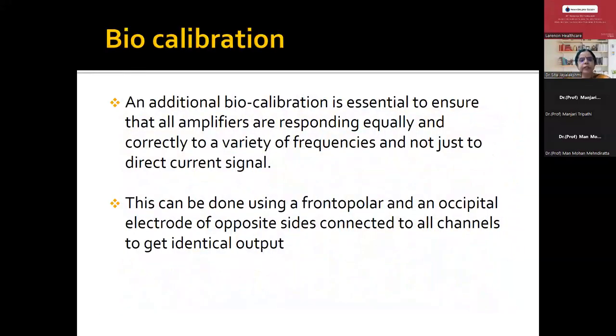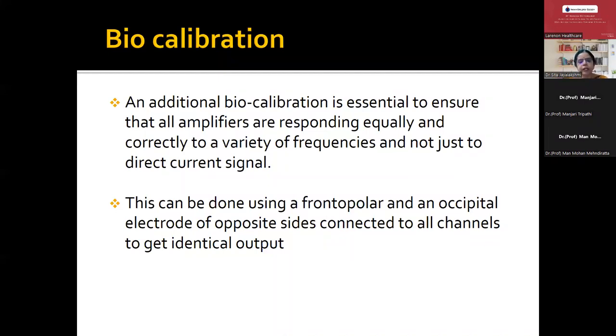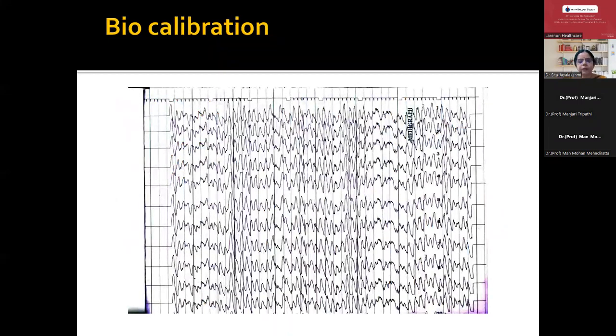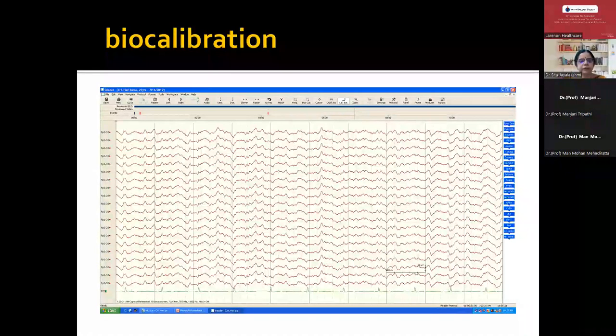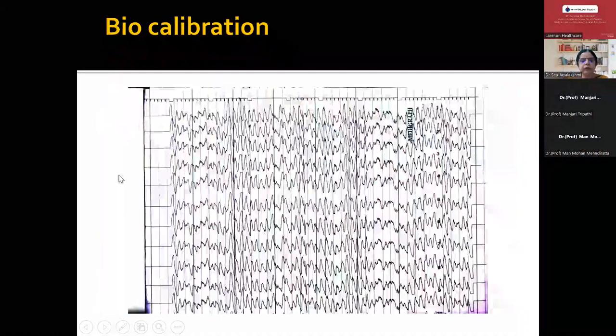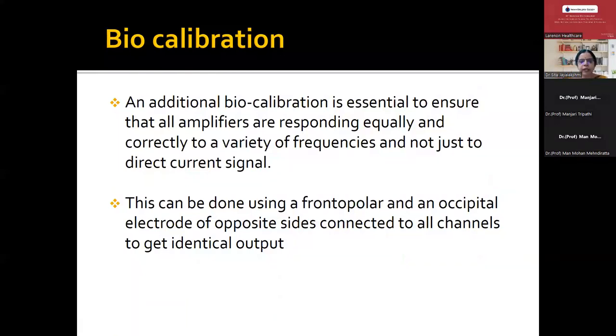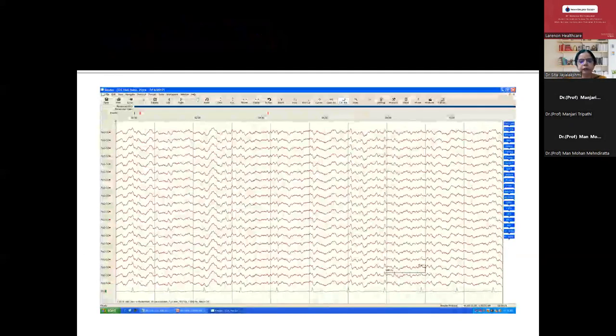The next step is biocalibration. In addition to mechanical calibration, biocalibration is essential to ensure all amplifiers respond equally and correctly to a variety of frequencies — not just to the direct current signal. This is done by using a frontopolar and an occipital electrode of the opposite side, both connected to all channels to get identical input. This is the biocalibration of an analog machine and this is the biocalibration of a digital machine. FP2 is connected to O2, and then these are connected to all channels to get identical output.